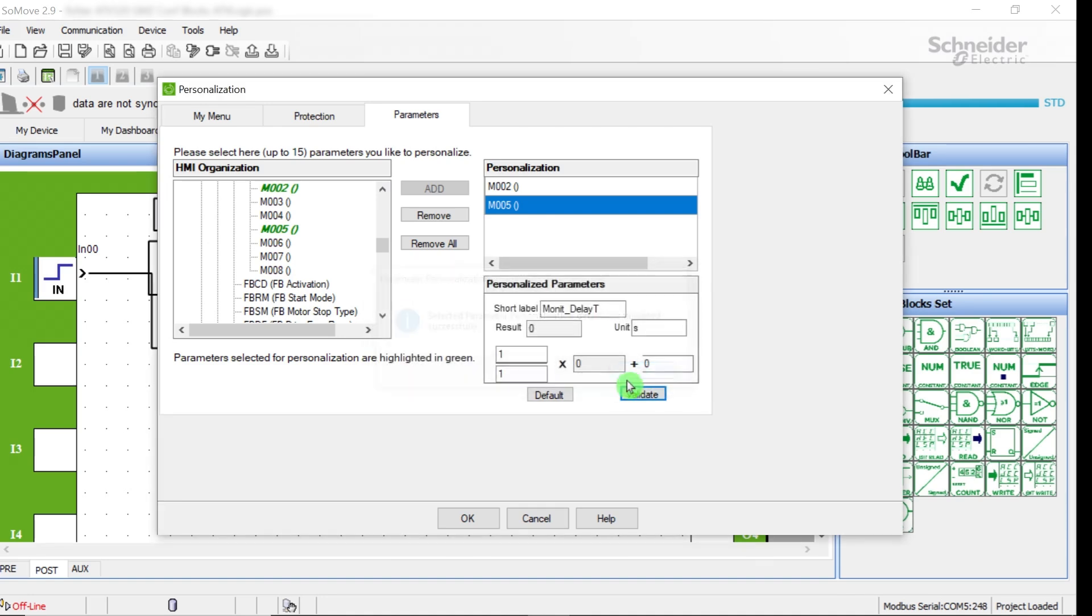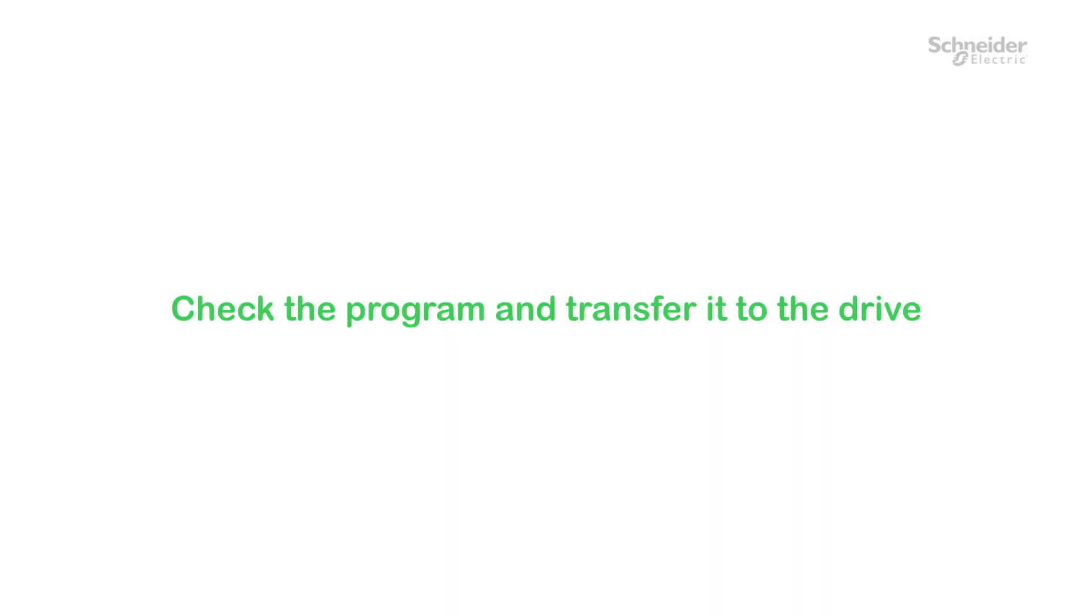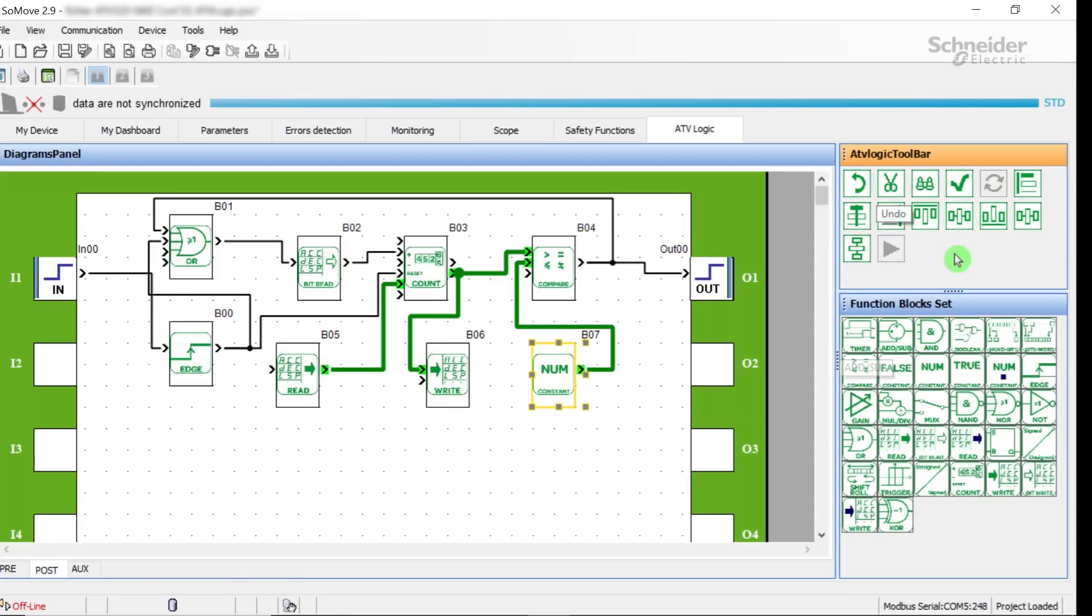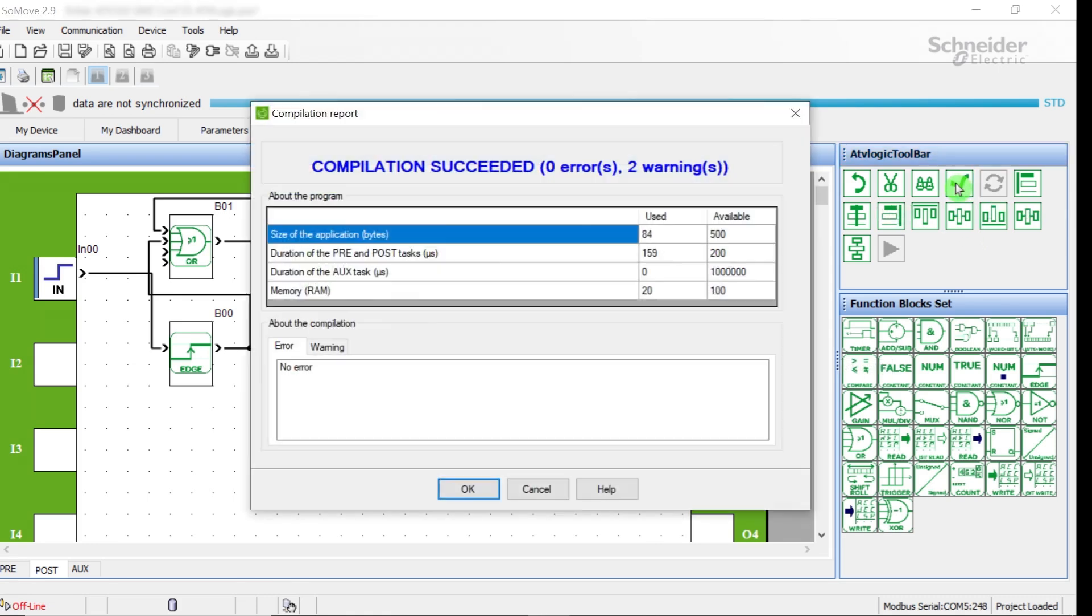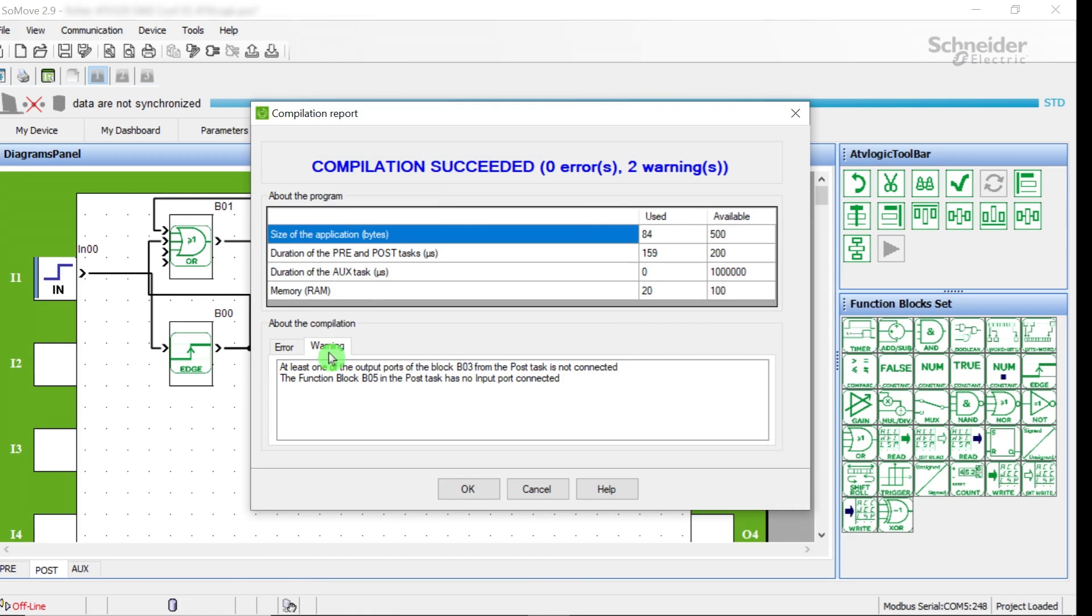The program is finished in local mode. Check the program and transfer it to the drive. Check the program to verify it conforms to the limitations. In the ATV logic toolbar, click on the Checkmark button to check the program. Errors and warnings are displayed in the corresponding tabs, Error and Warning. Correct the errors if necessary. Validate with the OK button.